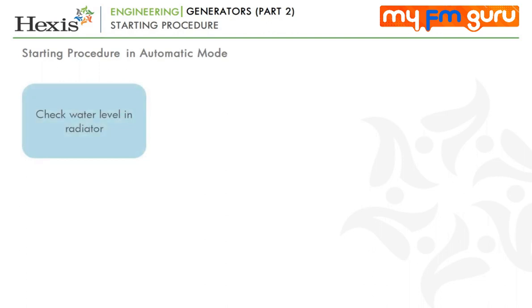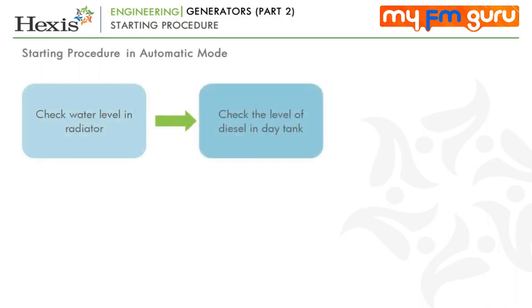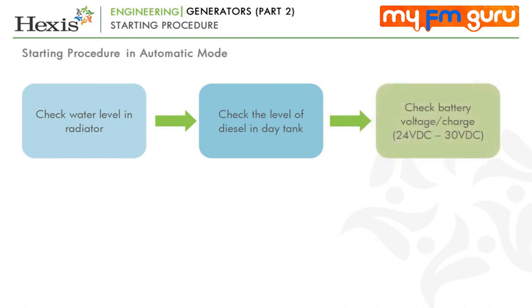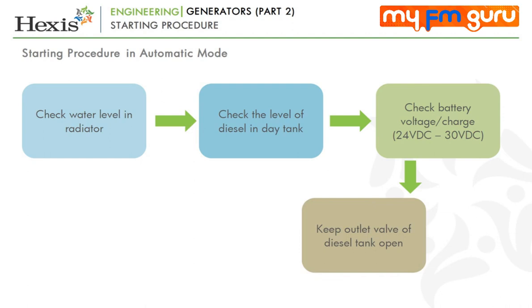A diesel generator has two methods of starting, manual and automatic. We will look at both of these in detail. Use the following steps given below to start the generator in the auto mode. Check the water level in radiator. Check the level of diesel in day tank. Check the battery voltage or charge. It must be in the range of 24 VDC to 30 VDC. Keep the outlet valve of diesel tank open.